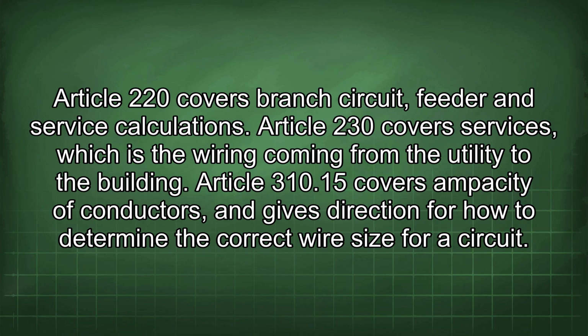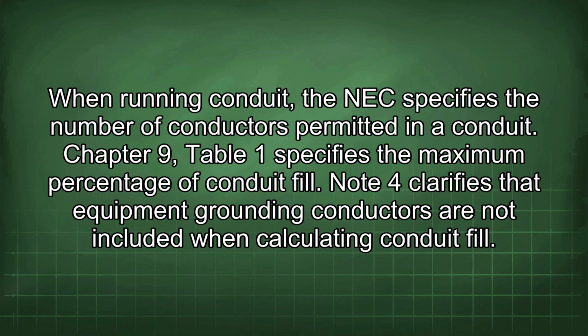Article 310.15 covers ampacity of conductors and gives direction for how to determine the correct wire size for a circuit. When running conduit, the NEC specifies the number of conductors permitted in a conduit. Chapter 9, Table 1 specifies the maximum percentage of conduit fill.